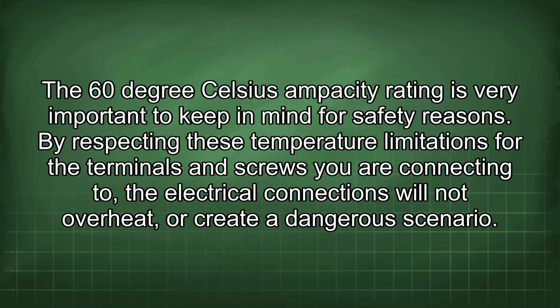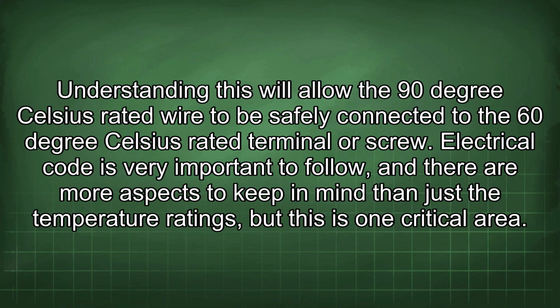The 60 degrees Celsius ampacity rating is very important to keep in mind for safety reasons. By respecting these temperature limitations for the terminals and screws you are connecting to, the electrical connections will not overheat or create a dangerous scenario. Understanding this will allow the 90 degrees Celsius rated wire to be safely connected to the 60 degrees Celsius rated terminal or screw. Electrical code is very important to follow, and there are more aspects to keep in mind than just the temperature ratings, but this is one critical area.